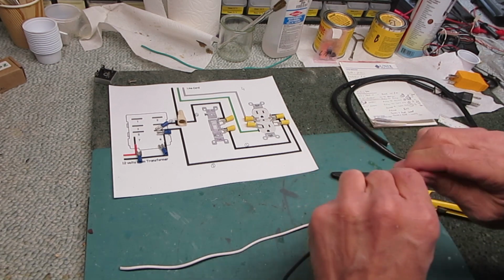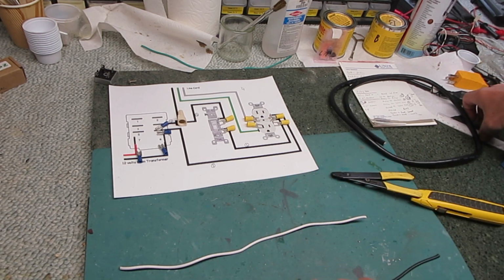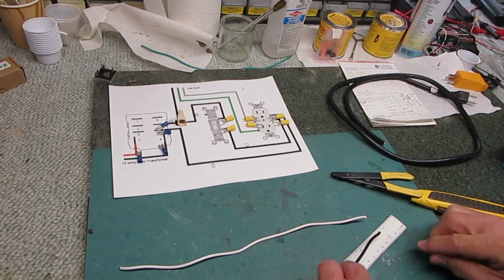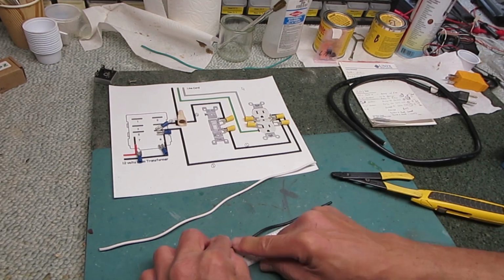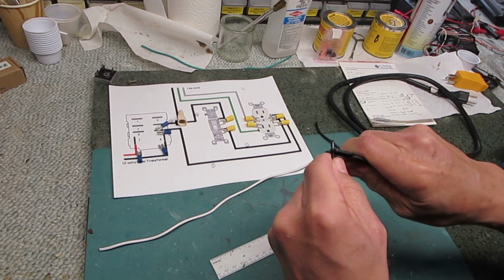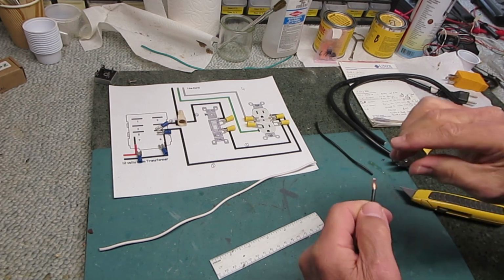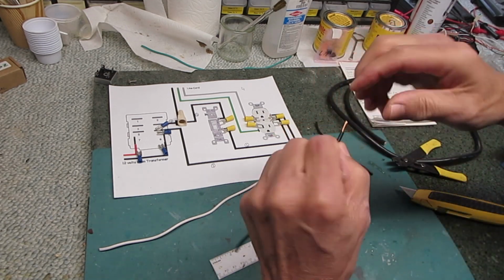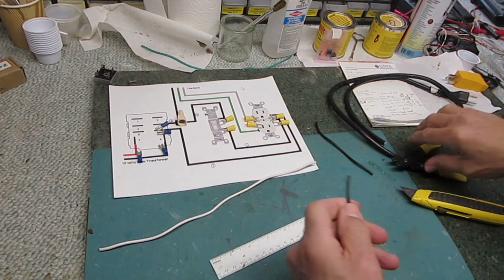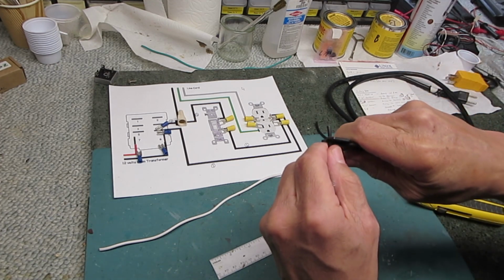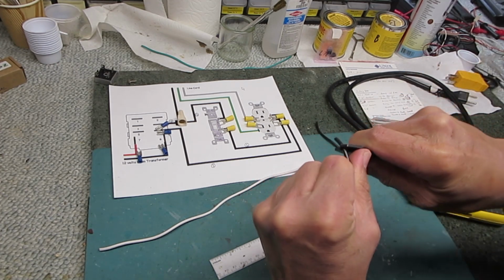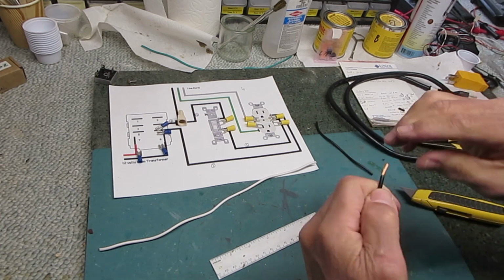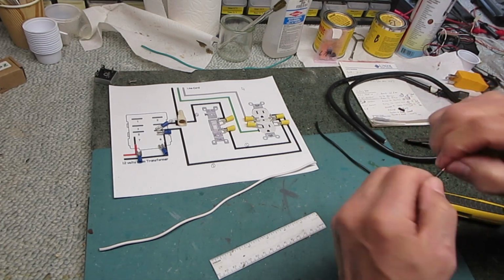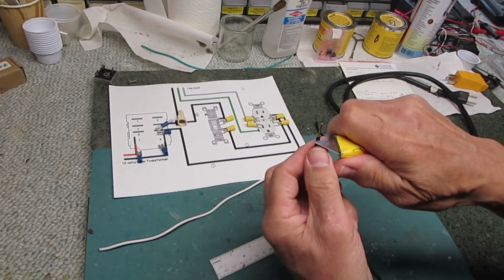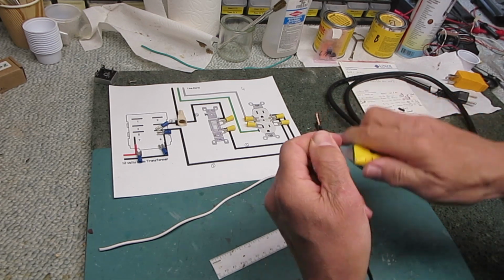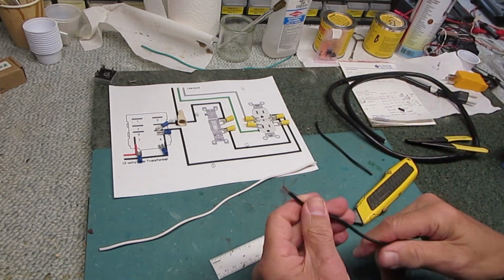Okay, let's start by making one of these, 7 inches. I'm going to strip the end. This is wire number 1. When you're doing stranded wire, you always want to twist the end after you strip the insulation off. If you don't have a wire stripper, you could take a knife and just kind of go into it little by little and then break it off.